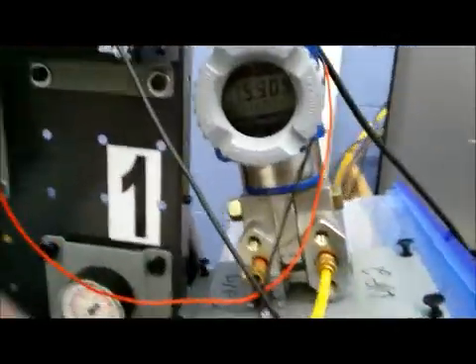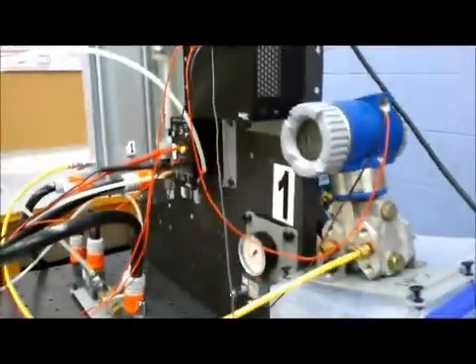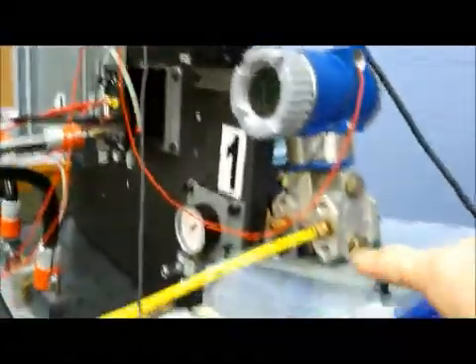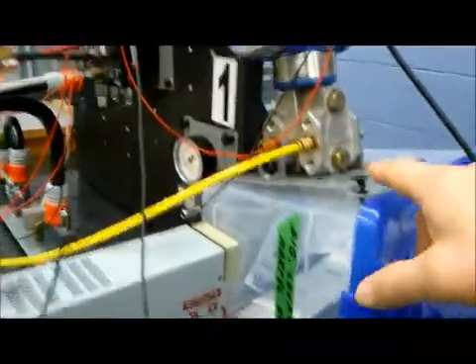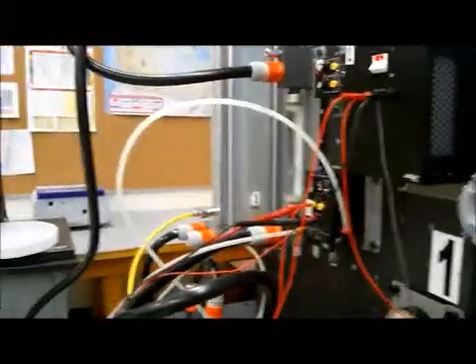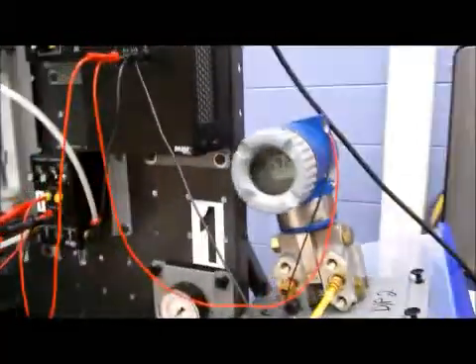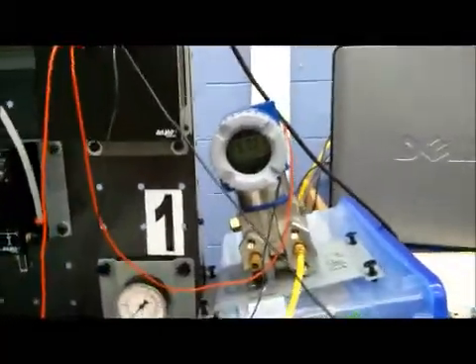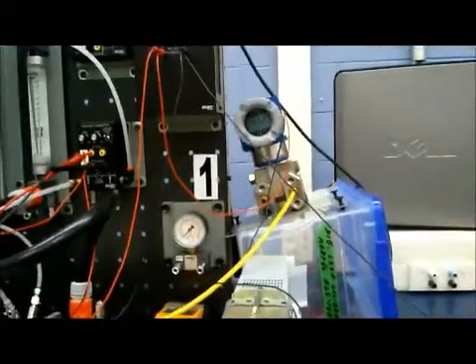Here's my actual fluid level that I'm controlling. And I actually had to bring the transmitter for level up. I had to set it on this to bring it up to the same level as the bottom of the cone, or else I'd be getting invalid readings for water cone.